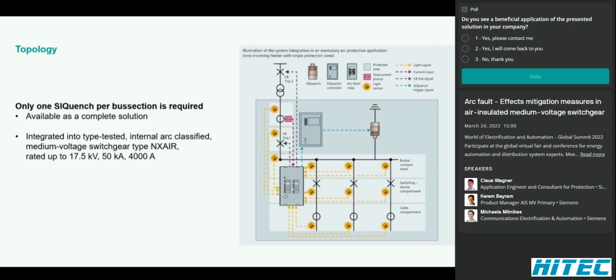As of today, SIQuench is available as a complete integrated solution into the internal arc classified air insulated medium voltage switchgear type NX Air up to and including 17.5 kV and 50 kA. It is located as fixed mounted in the busbar compartment. That is why only a single SIQuench per bus section is required and enough for the protection.